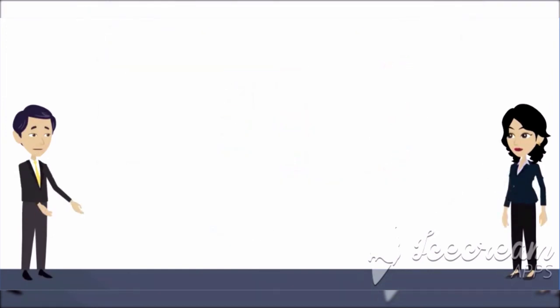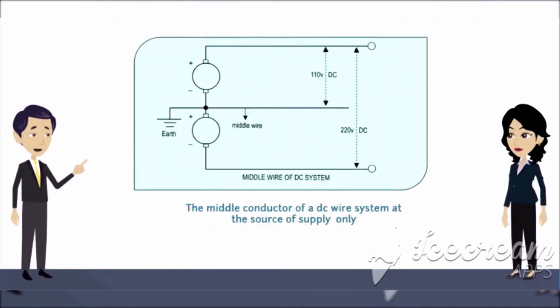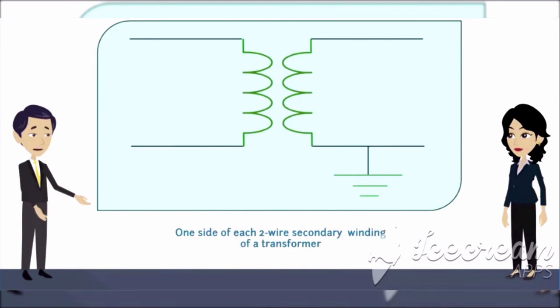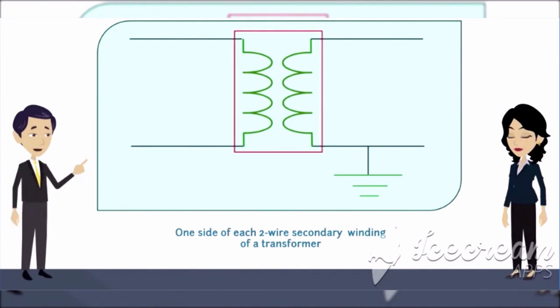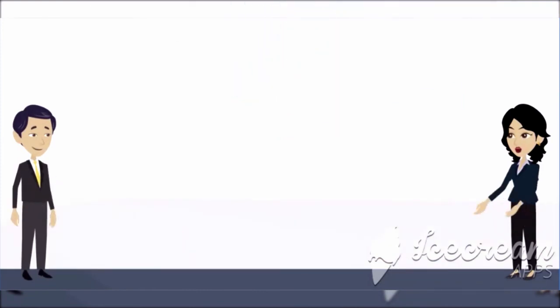Okay, next point is that the middle conductor of a DC wire system should be earthed at the source of supply only. As you can see here, this is the middle conductor and the neutral is connected. Yes, got it. Further, one side of each 2-wire secondary winding of a transformer also needs to be earthed. Let us see how. As you can see in the diagram here, this is a single-phase supply with the neutral point grounded. Understood. But is this all?